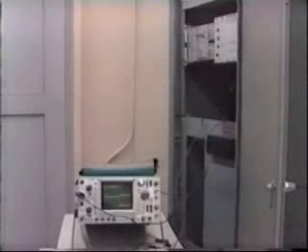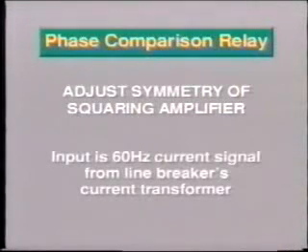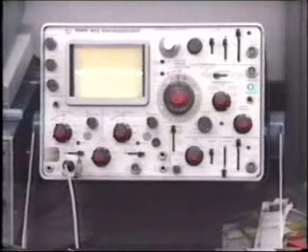Here is another practical example of the oscilloscope: testing a phase comparison relay. The manufacturer's instruction book tells you to adjust the symmetry of a squaring amplifier whose input is a 60 hertz current signal from a line breaker's current transformers. You can obtain the waveform on the scope and adjust the appropriate potentiometer for equal on and off times of 8.33 milliseconds each. A regular multimeter could not give you the necessary picture for such a precise adjustment. The phase comparison relay also needs a propagation delay adjustment to delay the local CT signal to exactly match the CT signal from the line's remote end.